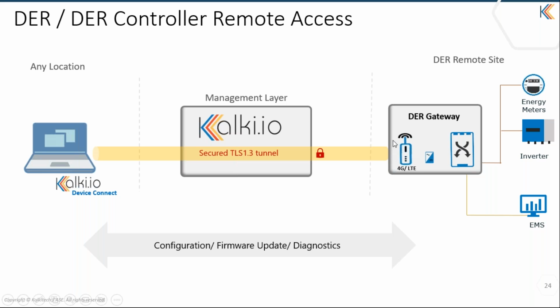Because of strict firewall policy, no inbound connection is allowed from any users to the gateway. Only inbound connection is through the secure tunnel, created from the gateway using the pre-installed client authentication. The gateway creates an outbound connection to Kalki.io and establishes a TLS 1.3 tunnel, so remote access is only through this tunnel, ensuring nobody from the external, WAN, or internet network can directly connect to the gateway and access field devices.